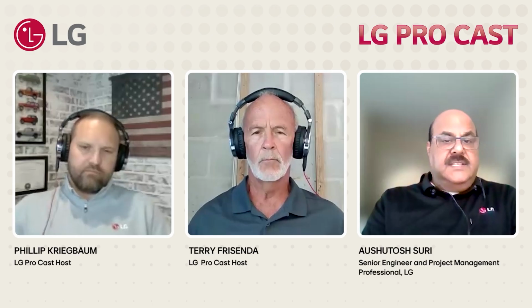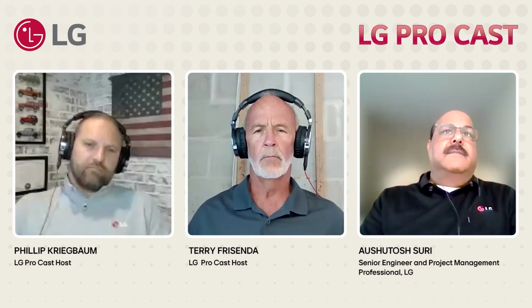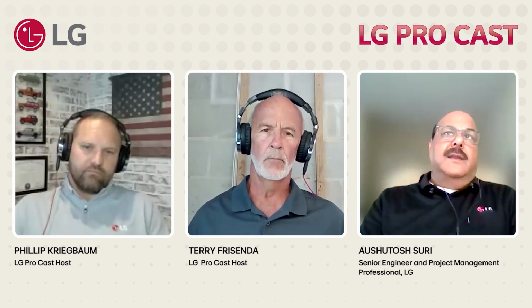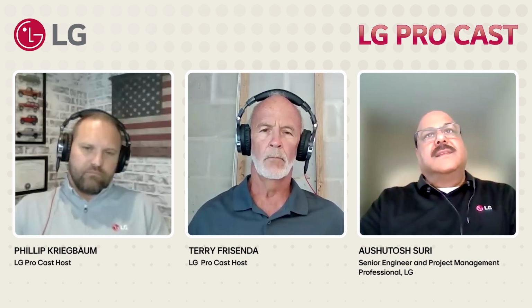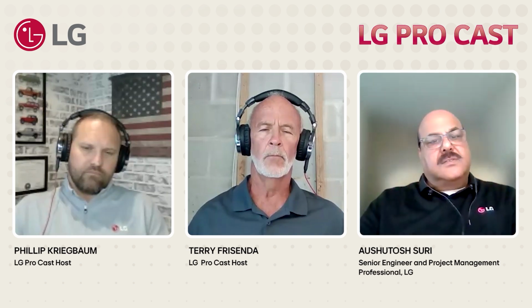So we have 2 EEVs, electronic expansion valves. One is in the indoor unit, one is in the outdoor unit. How does it help? With the embedded EEV in both indoor and outdoor unit, the system allows us to use the existing pipeline. Say, for example, when we have a retrofit job where you already have an indoor unit which you want to change, but the pipes are embedded in the wall.